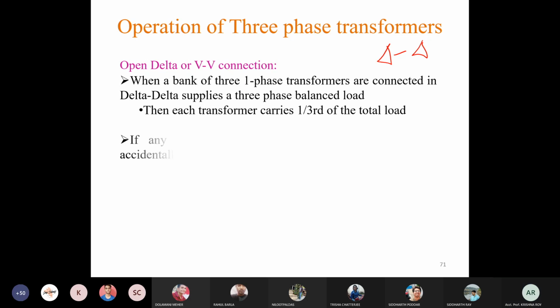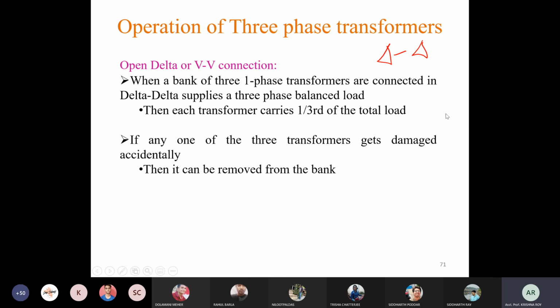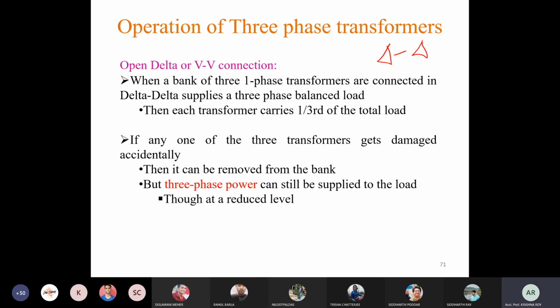Okay, assuming we are having a balanced load system. Now if any one of these three transformers gets damaged accidentally or any other way, then what happens? Then we can remove that faulty transformer from the three phase bank, and we can still supply three phase power to the load, and this will be at a reduced level.